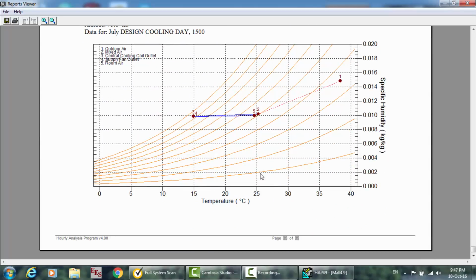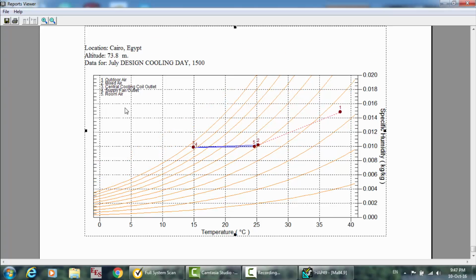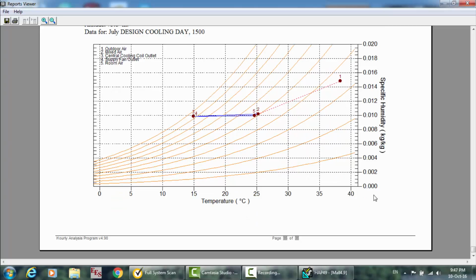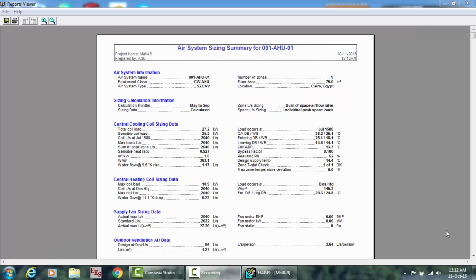And here the psychrometric chart, the outdoor air point 1, and the mixed air point 2, then the central cooling coil outlet, and then the supply fan outlet, and then the room air, number 5, is around 24. Okay, ladies and gentlemen, this is the report. Notice that the water flow here for cooling is 1.17, and for heating is 0.23 liters per second of water. So if this is a two-pipe system, you have to design according to the largest number.